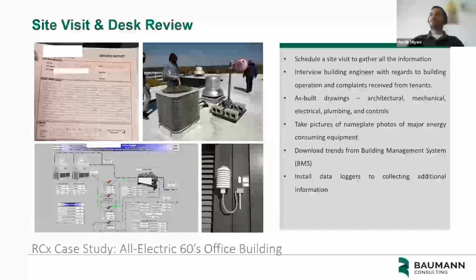Next step, we look into the building management system, which is a computer-based control system installed in buildings that controls and monitors the building's mechanical and electrical equipment. It provides insight into what the current set points and schedules for each and every equipment in the building are. Some BAS do have trend data capability as well. It provides a better insight into the building performance on a time interval basis, like it can be for minutes, days, or throughout the year as well.